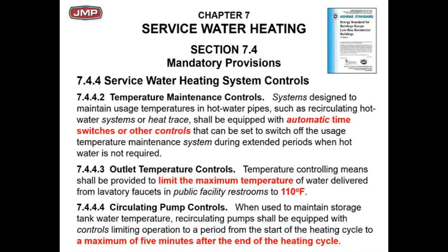Next statement is they say, let's hold the maximum temperature to 110 degrees. Most of us who have been in the business would probably say about 105 at the actual fixture is okay. 110 is probably okay, but limit it to 110.